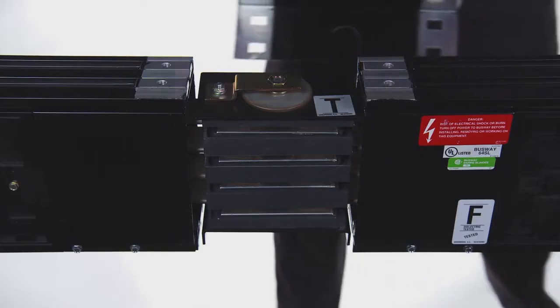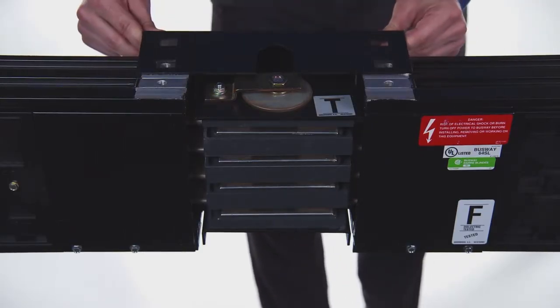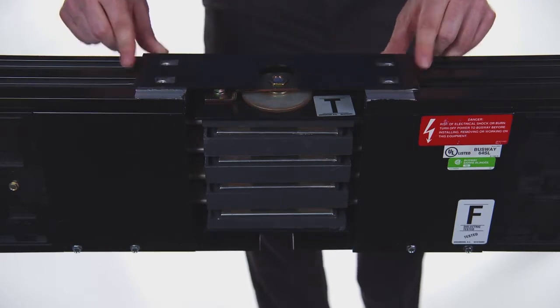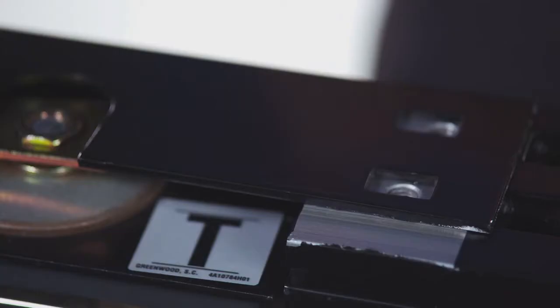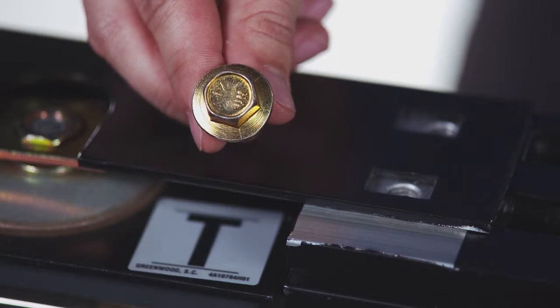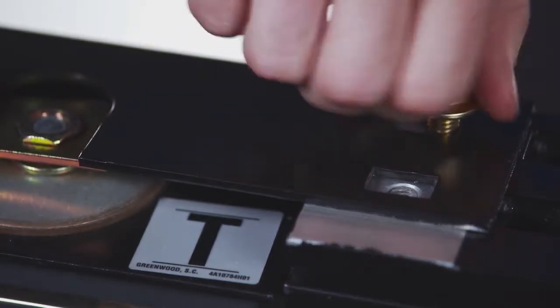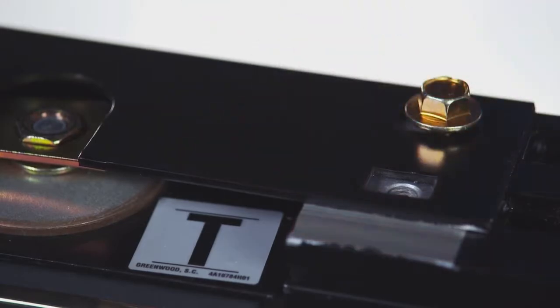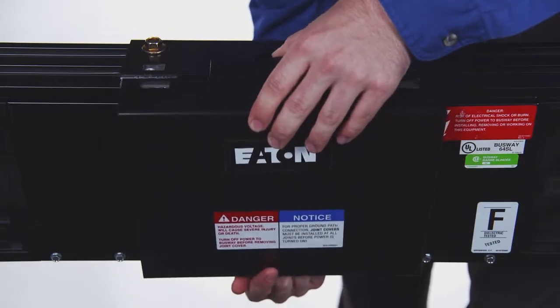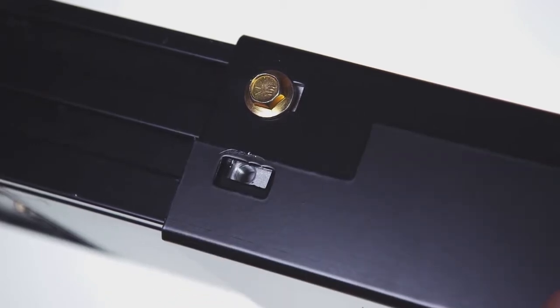To install the joint covers, attach the rear joint cover to the end blocks at the end of the busway housing. Use the flanged head hex bolts provided. Only install the bolts closest to the rear joint cover at this time. The front or single hole joint cover sits on top of the rear or double hole cover on both sides of the busway, like this.